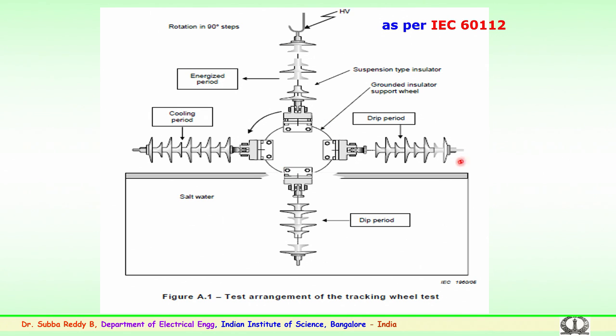As per the standard, the rotating wheel timing is: 40 seconds dip in the contaminant, then 8 seconds transition from dip to drip, then 40 seconds drip period, then 8 seconds transition to high voltage contact, then 40 seconds of high voltage contact, then 8 seconds transition, then 40 seconds of cooling. The total cycle is 40×4 = 160 seconds plus 8×4 = 32 seconds, giving 192 seconds per rotation cycle.